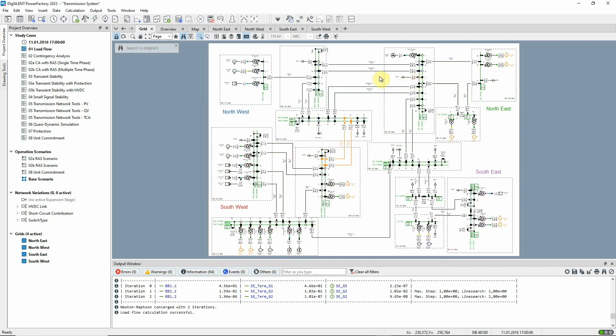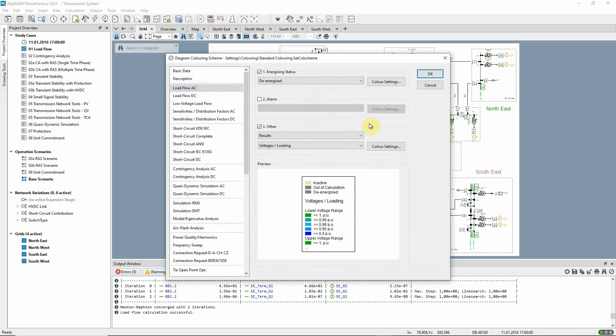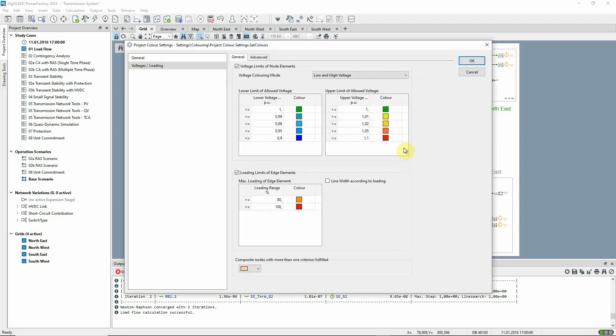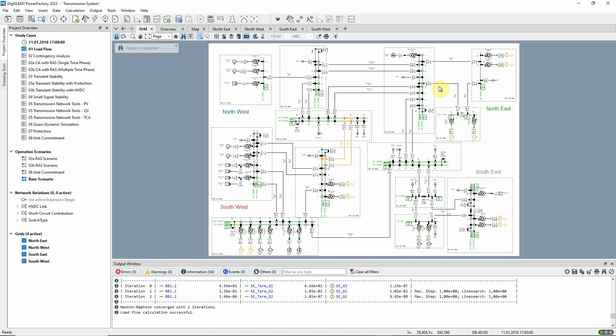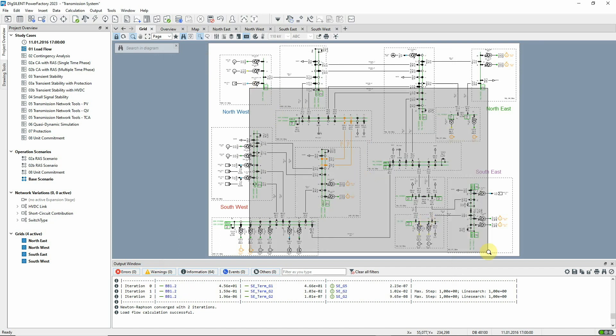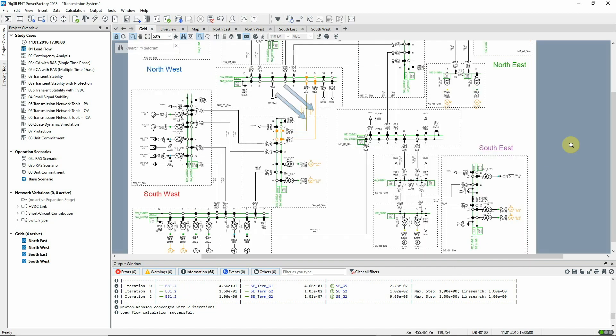Notice that different graphic coloring options have been selected for when a load flow has been run to show the voltages of busbars relative to nominal and the loading of edge elements such as lines relative to their thermal ratings. You can see how the lines connecting the north-west grid to the south-west grid are colored orange. They're heavily loaded at over 91% of their rating.